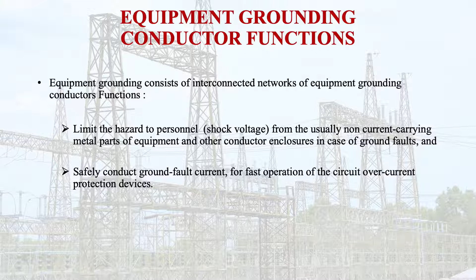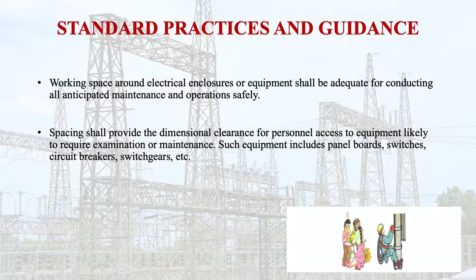Working space around electrical enclosures or equipment shall be adequate for conducting all anticipated maintenance and operations safely, including sufficient room for rescuing injured personnel. The spacing shall provide the dimensional clearance for personnel access to equipment likely to require examination or maintenance. Such equipment includes panel boards, switches, circuit breakers, switchgear, etc.